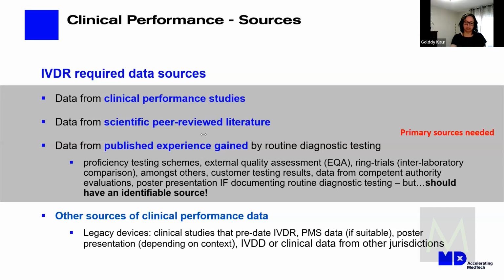Okay, I'll check that out. So you're saying there is an equipment justification there. I'm not an expert in IVDR, so I have to check it myself. That's fine. There may be a reason, but it all comes down to the definition of what an IVD is. We would need to look at the device: what does it actually do in the lab? If it is used in a way that helps an IVD achieve its intended purpose, it could be an accessory to an IVD, and that falls under the IVD regulation. We would need to look at it to provide you more information.